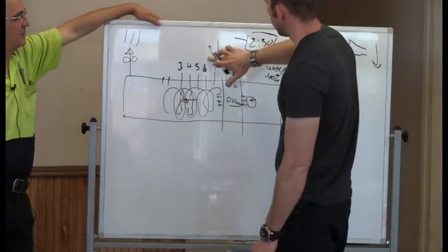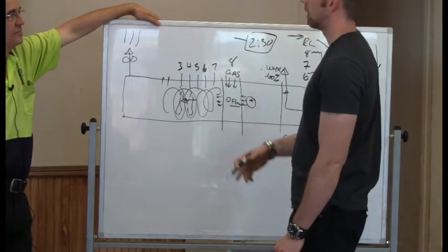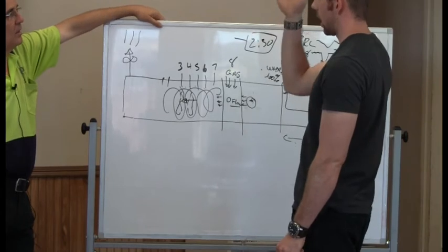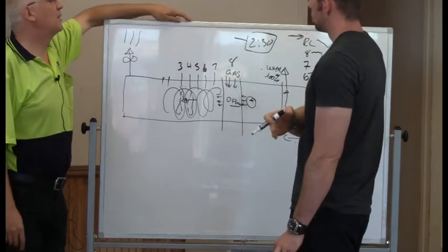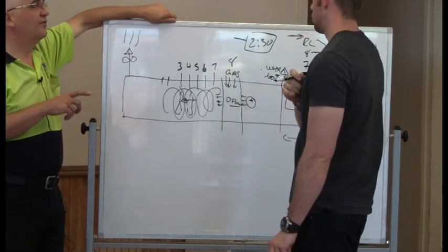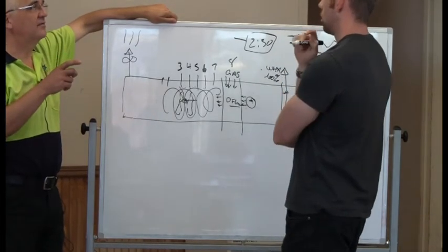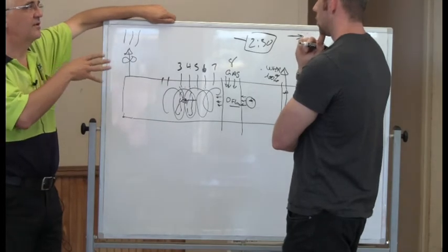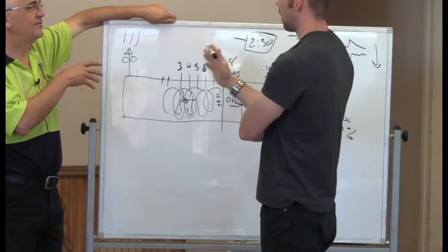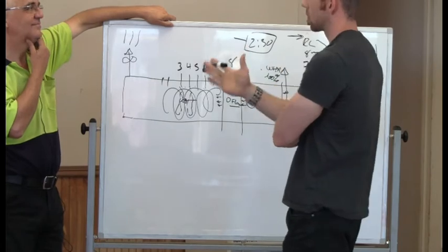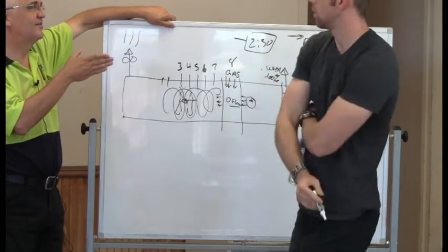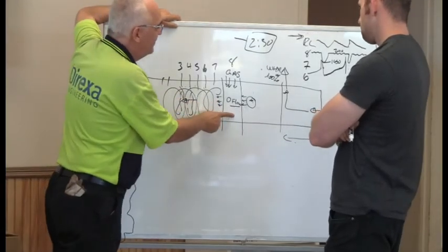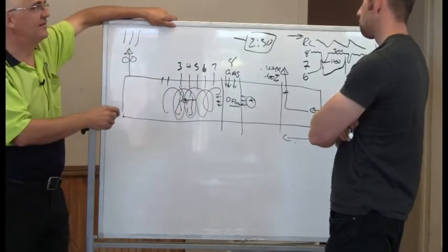So on that fuel cutoff, basically just let it cycle like it normally would, but just cut the fuel off, right? Because I've got an ASCO valve. Actually, you would have to force it, because if you cycle it, what I don't like is it's going to create some sort of pulsing through the kiln. Right, it's supposed to make that pressure wave, right? So if I force the air during the flashing, it helps me stabilize my zero flow.